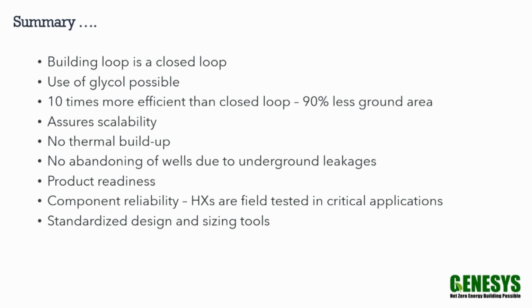There is no thermal buildup because you are constantly recharging and using a constant temperature water to draw and do the heat transfer. There is no thermal buildup at the borehole, so you don't have to deal with balancing loads, which is typically a challenge in closed loop systems.